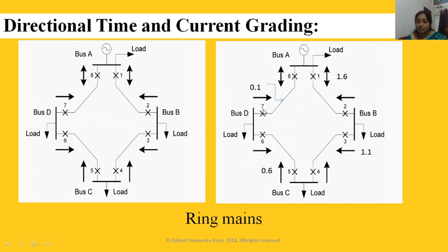Okay, suppose this fails to operate, which is the next relay to operate? The fault is fed like this. So definitely this will not operate. Why? Because the fault current direction is into the bus while the tripping direction is away from the bus, so this will not operate. Let us see. Fault current is like this, tripping direction is the same, so this will operate. Now here again a 0.5 second delay is given, so 0.1 plus 0.5, it is 0.6.